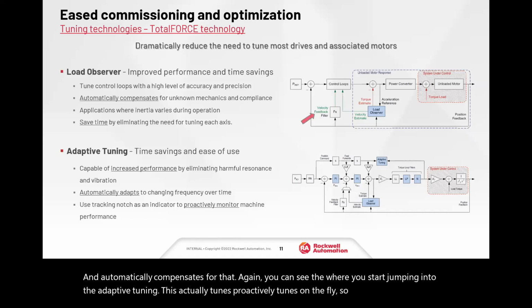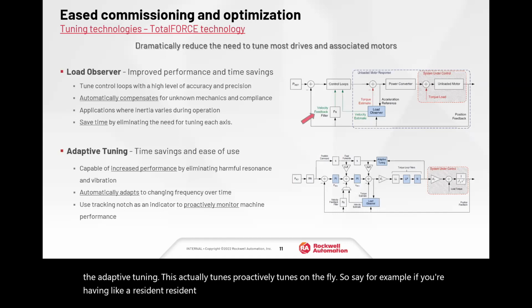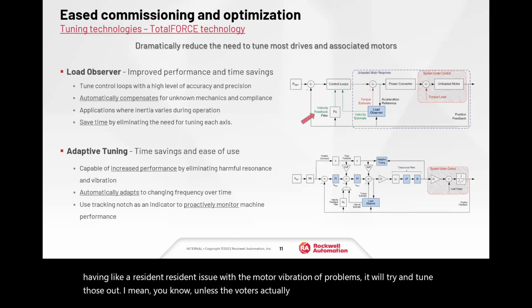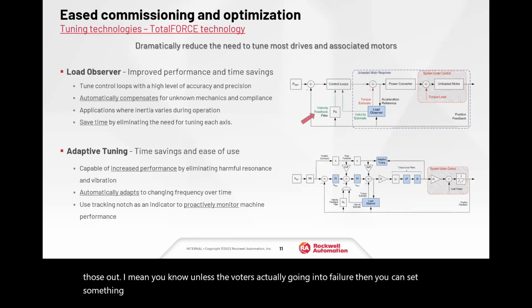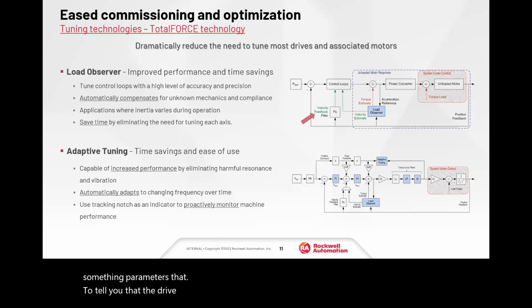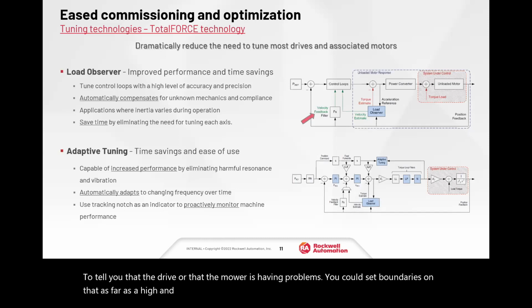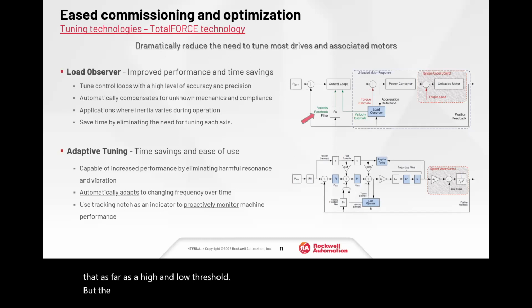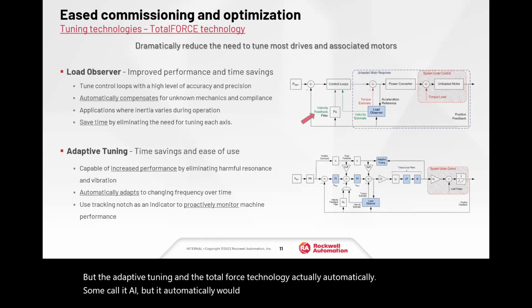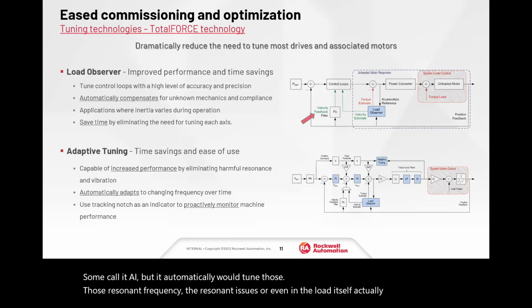So say, for example, if you're having a resonant issue with the motor or vibrational problems, it will try and tune those out. Unless the motor's actually going into failure, then you can set some other parameters that will tell you that the motor is having problems. You can set boundaries on that, as far as a high and low threshold. But the adaptive tuning and the Total Force technology, some call it AI, but it automatically will tune those resonant frequency or resonant issues out, or even in the load itself, will tune those out.